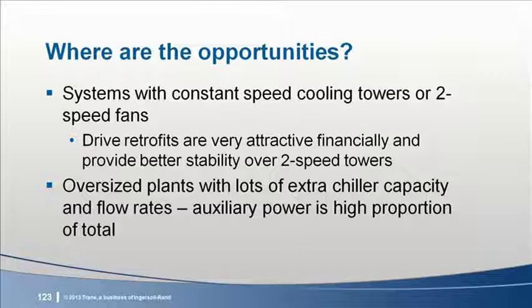Oversized plants are good places to look because not only is there extra chiller capacity, there is excess pumping capacity, which makes the auxiliary power a higher proportion of the total energy. They also have big pipes, so the pumping energy savings at low flow will not be reduced by the temptation to reduce pipe size and trade in some of the energy savings for first cost savings.